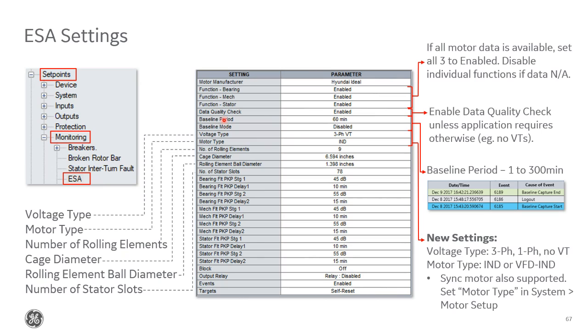Then we have the two baseline settings. This is something that we updated in firmware version 2.7 as well. The period options used to be something like 24 and 48 hours. Now we've left it configurable anywhere from 1 to 300 minutes, which is particularly useful if you're trying to test this out during commissioning, for example. You can set this baseline period really low just to have something stored and then see it in monitoring mode and see what you can do in monitoring mode, all the screens you can see from it. And then after that, you can clear the records and then up this to something more usual, like 60 minutes, which is the recommended minimum, and then put the relay back in service.